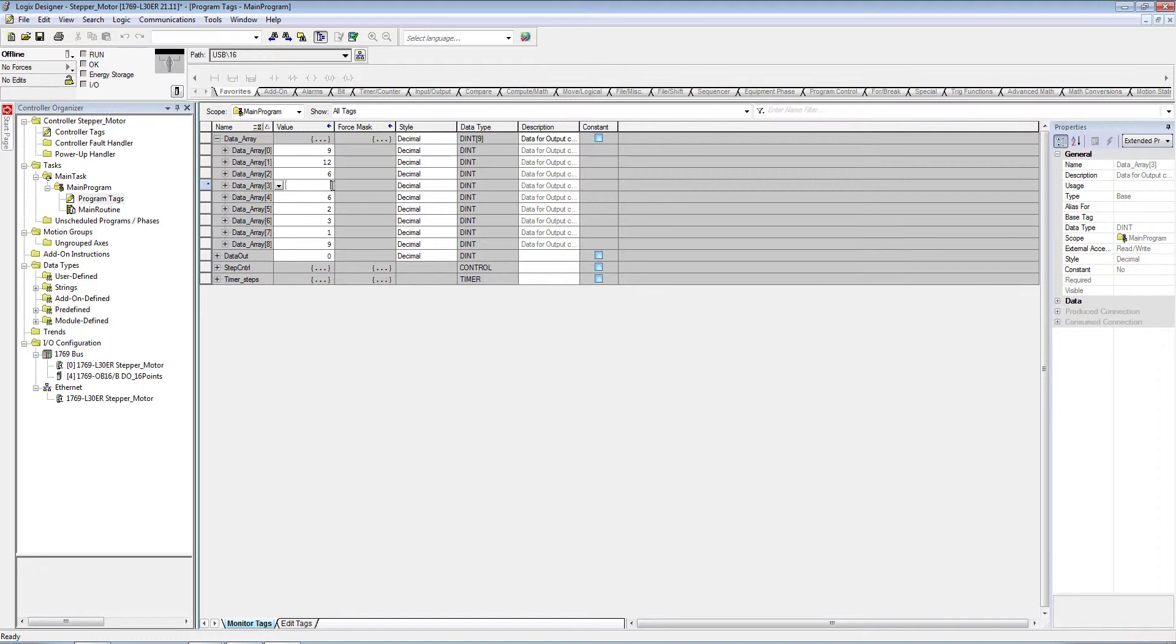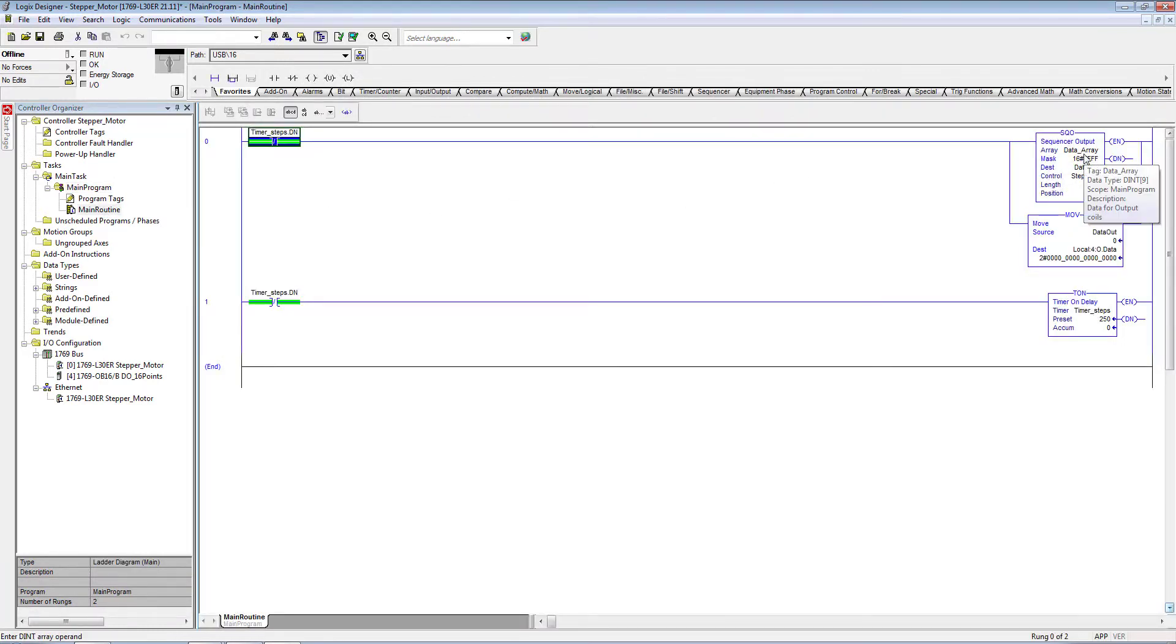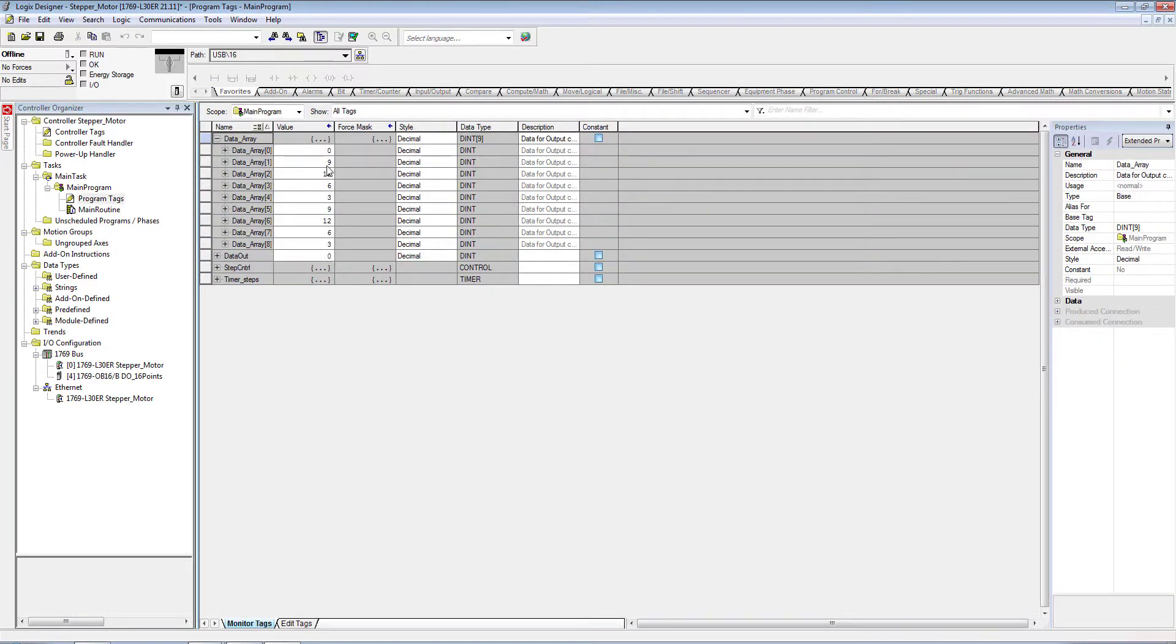There was a small problem - the sequencer output always skips the first element in the data array. The first element should be zero, then our main data should be in first place. Whenever our sequencer output is triggered, it will point to this data.